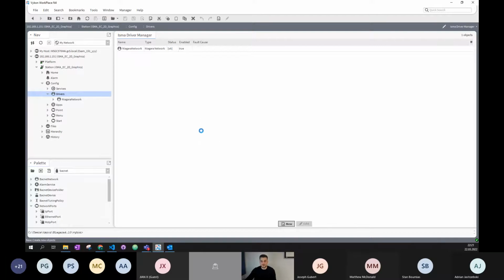First of all, we need to do some classic configuration steps that we always do. We are going to use Modbus RTU, so we need to select the correct protocol, which is Modbus Async network. So this is Modbus RTU. Yeah, so we have a little configuration ahead of us because there is an error: there is no port selected. So this is standard. We just need to make sure that we are communicating at the correct speed, which is this one, and the communication port, which is COM1. After that, I should be able to get the OK status, which has happened right now, as you can see.